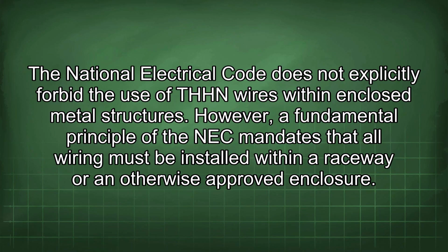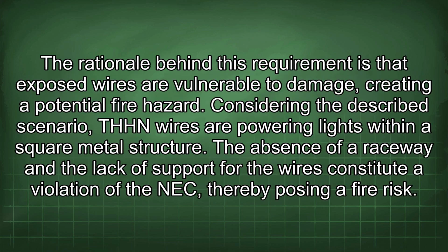The National Electrical Code does not explicitly forbid the use of THHN wires within enclosed metal structures. However, a fundamental principle of the NEC mandates that all wiring must be installed within a raceway or an otherwise approved enclosure. The rationale behind this requirement is that exposed wires are vulnerable to damage, creating a potential fire hazard.